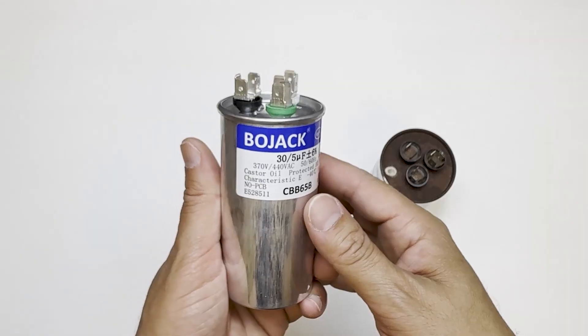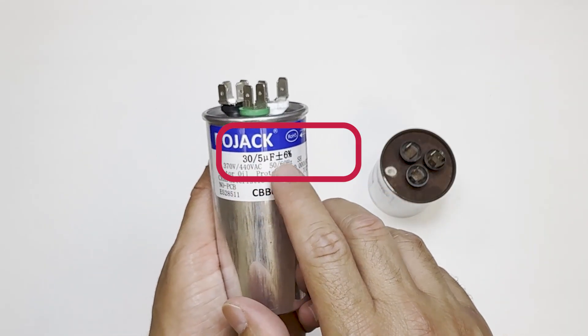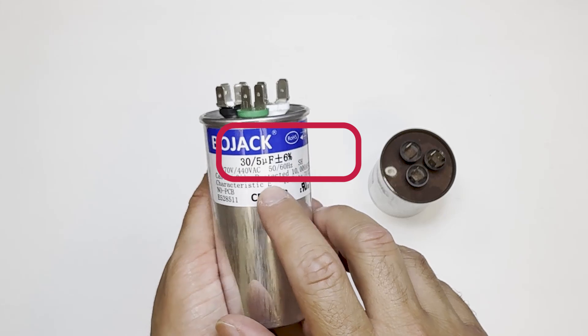The new capacitor has the same terminals, C, fan, and herm, and the same ratings as the old capacitor, 30 by 5 microfarads plus or minus 6% and 440 volts.